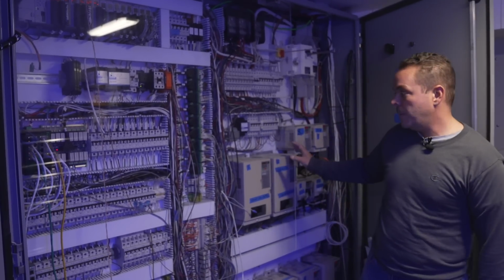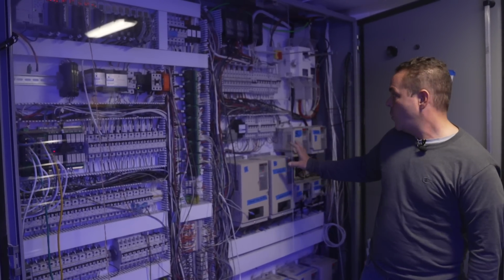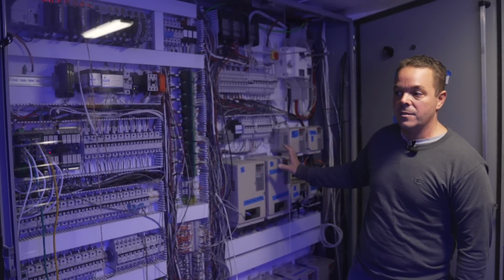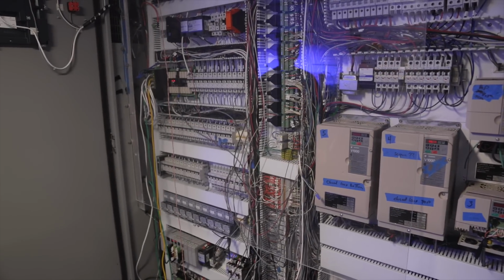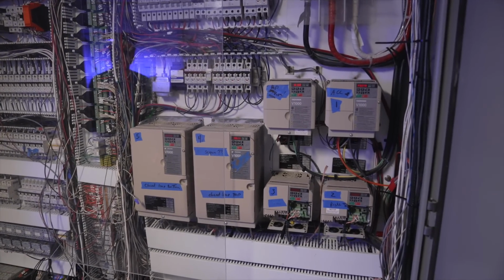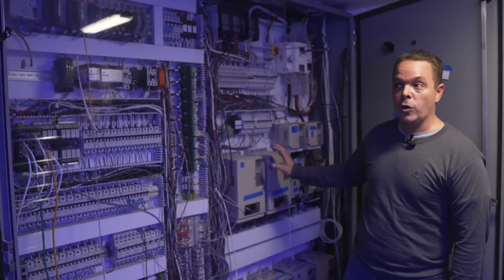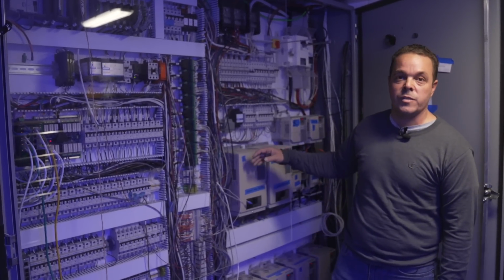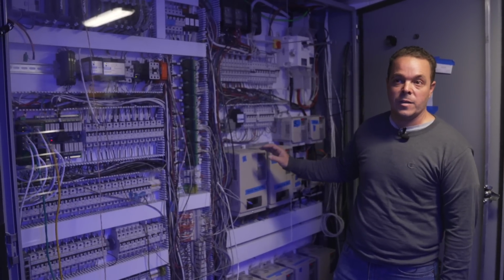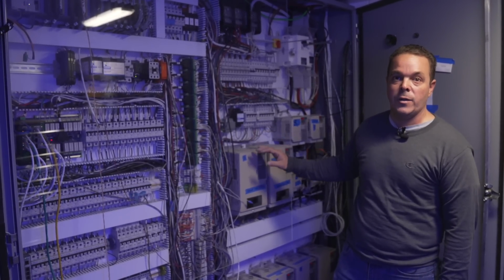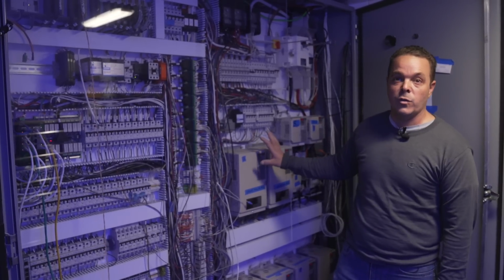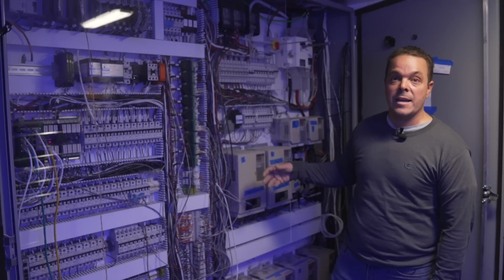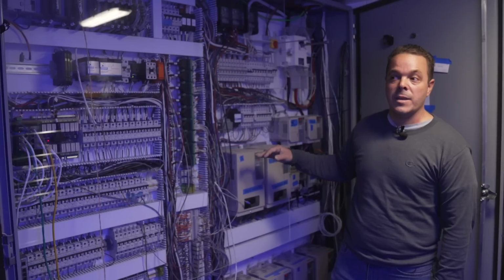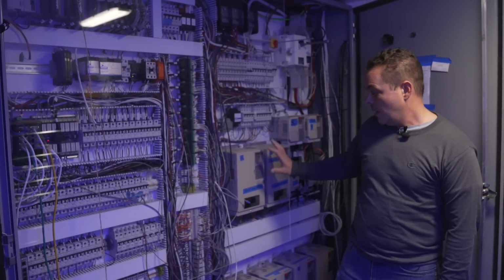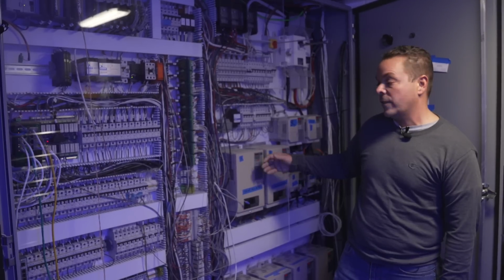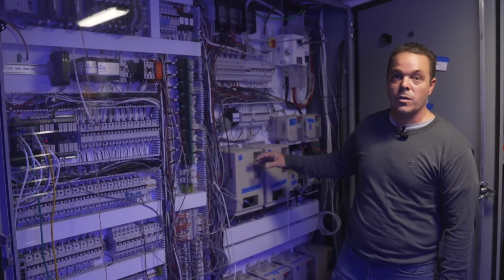Bigger motors, being that they're 3-phase motors and we didn't have that available here, we're actually using a VFD to replicate that 3rd phase. The VFD takes regular household power and makes it into more of an industrial type application. It also is able to control the hertz at which the electric cycles, which therefore controls the speed at which the motor is spinning. So rather than turning a valve down, it can control the flow. We can speed up or slow down each motor individually so that we can dial in the exact flow rate we're looking for. And in terms of something like the sand filter, as it gets dirty, we're able to keep a consistent flow rate with these devices as well. They also protect the motors thermally, because if the motor is drawing too much energy, it will shut down to protect the motor.